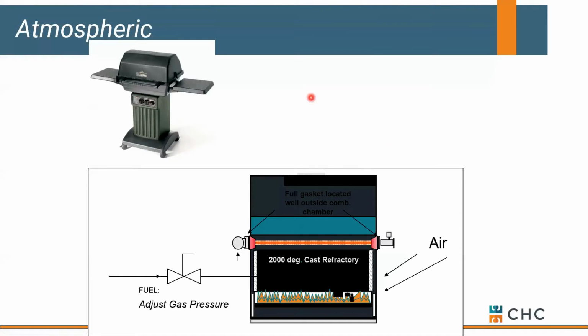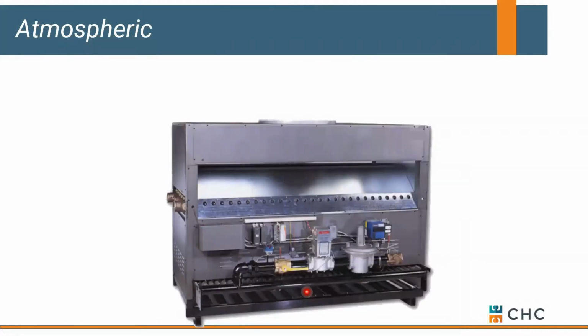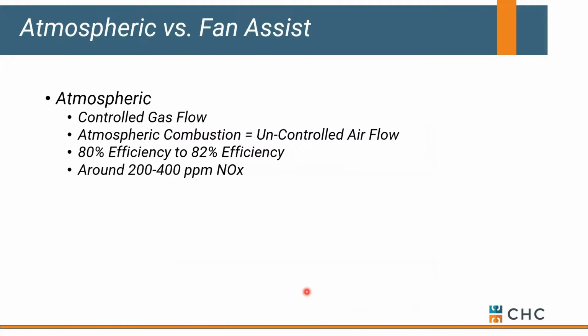So really it's very similar to a barbecue. The only difference is we don't have nice smells coming off of it, and you have to get rid of the toxic air that's coming off of our combustion. So very reliable, really easy to troubleshoot. If you've got a source for gas and you've got spark and water flow, you tend to have combustion and heat in your building. Now there's some downsides to atmospheric.